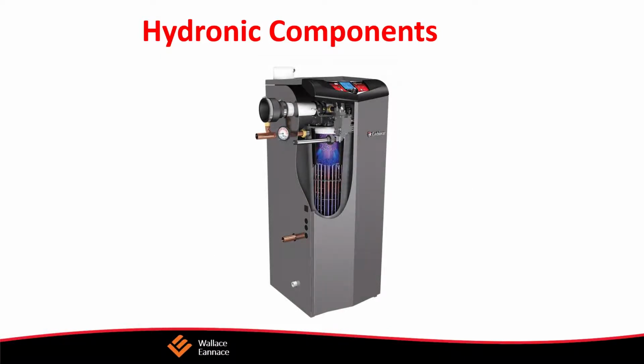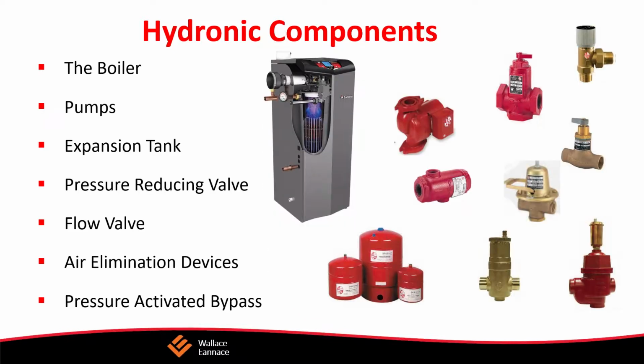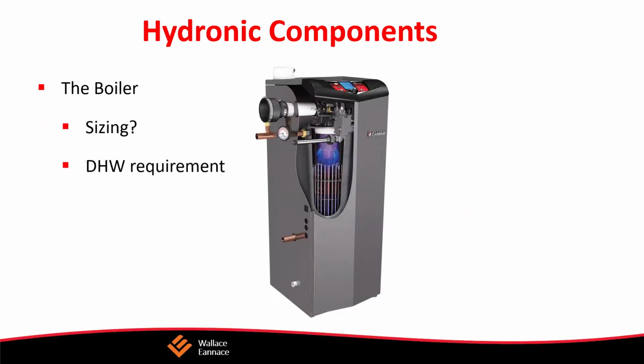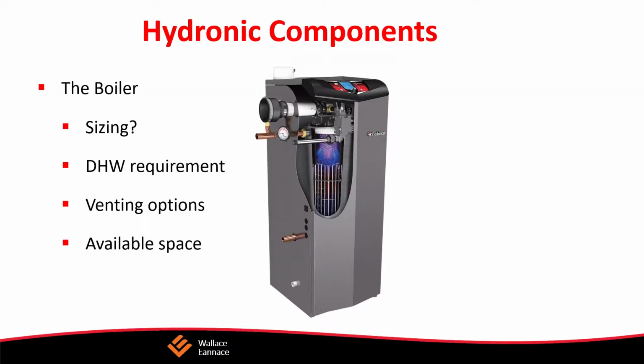So let's start with the boiler. With the boiler, when selecting the boiler, the first thing we want to do is figure out what size boiler we need. So our concern is the domestic hot water requirements. What are we going to need for domestic hot water requirements? How are we going to vent the unit? How much space do we have for the unit? These are the questions that we ask ourselves when trying to select a boiler for any given building.